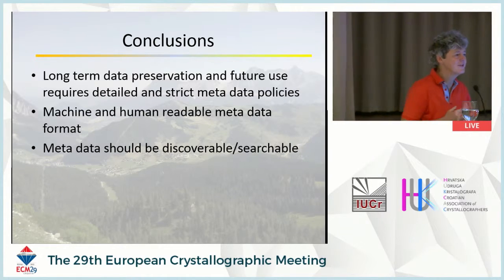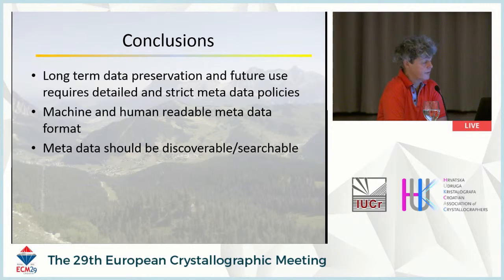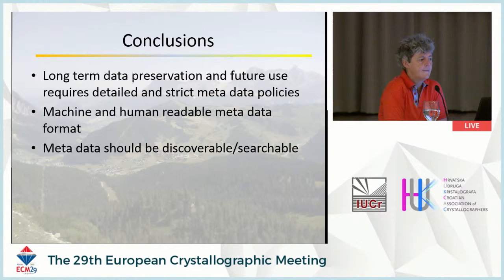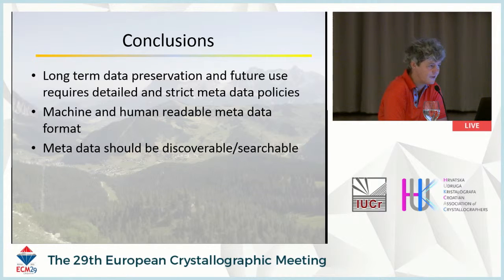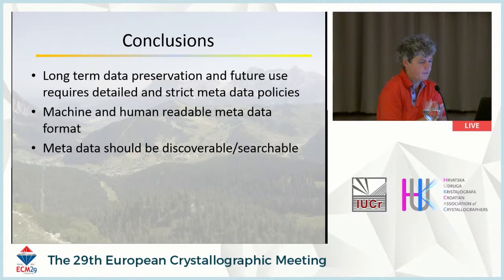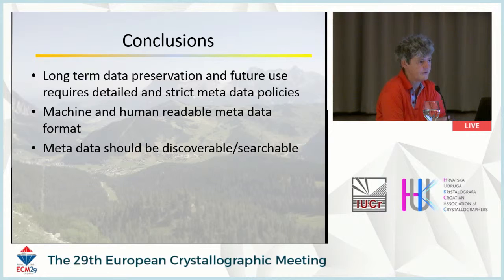The speaker agreed: it would be great if all manufacturers adhered to a single format — CBF or imgCIF — but it simply doesn't happen. Most manufacturers do have well-documented formats, so you can decipher which format it is, but with so many dialects, every software package like HKL3000 or EVAL has to cope with all of them. It would be much better if the header were at least in imgCIF. On that note, the session broke for coffee.